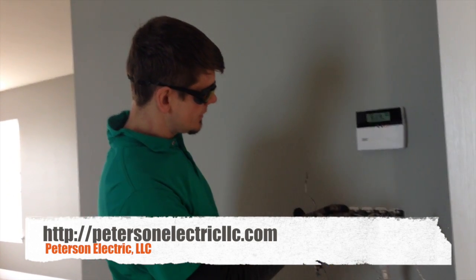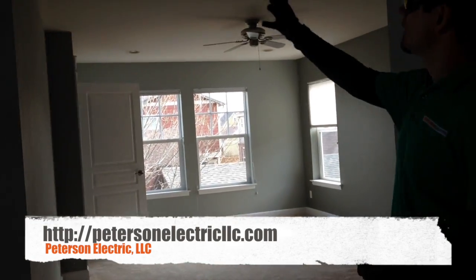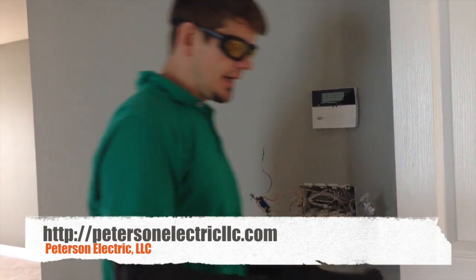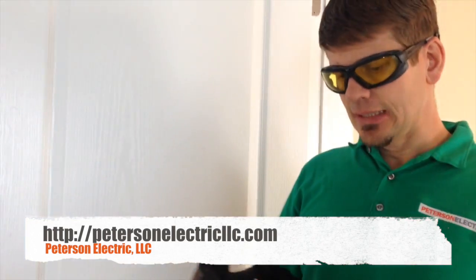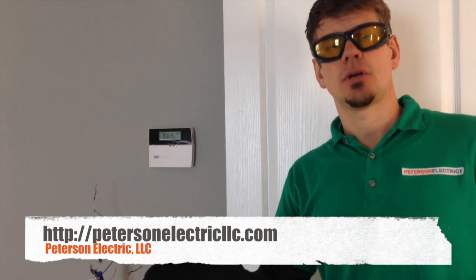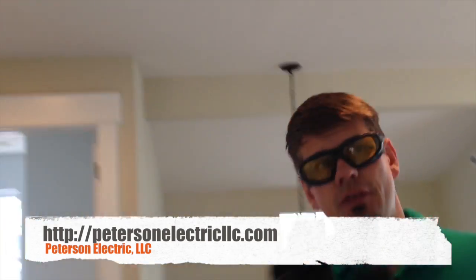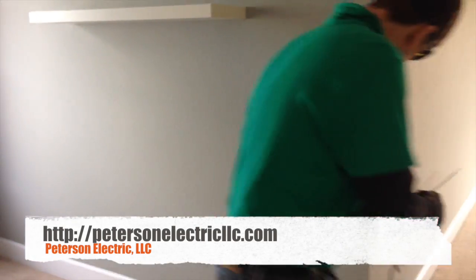So here's what we found — I think I found the issue. This is a four-gang box. The panel is that way, the retreat is here, the master bedroom suite is there. The lights are off in the bathroom, which matches code. All of these plugs are on, and all of these plugs in the entryway right here are on. I turned off breaker 19A, which was a non-arc fault on the retreat side, and literally when I turned it off, nothing turned off. I came back up, left the master bedroom on, then swapped the master bedroom circuit for the retreat — same thing. Everything I showed you in the other video is still on, all the way around. Nothing changed.